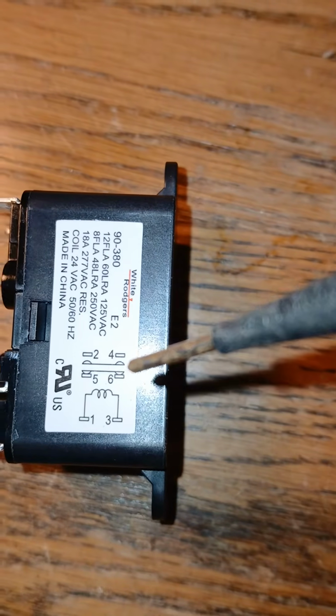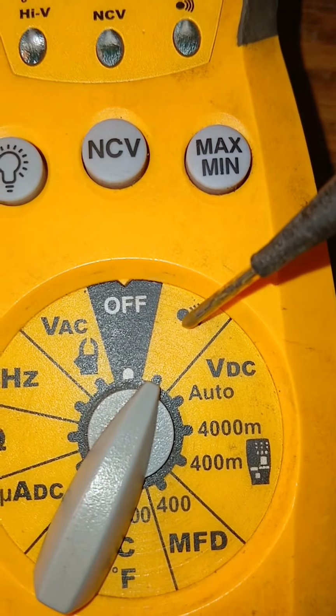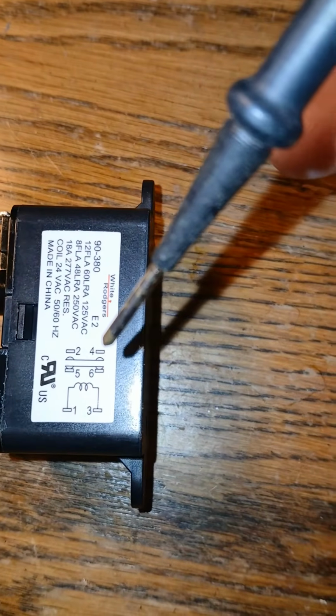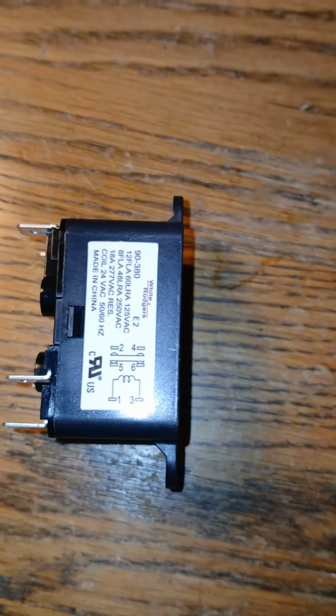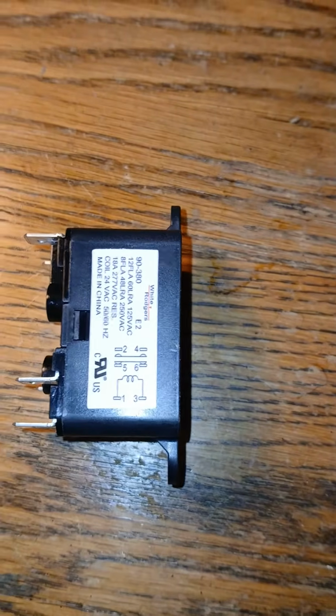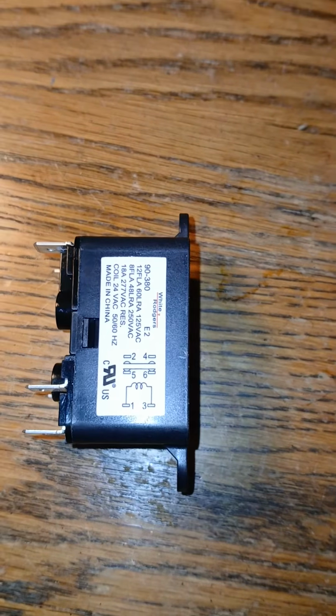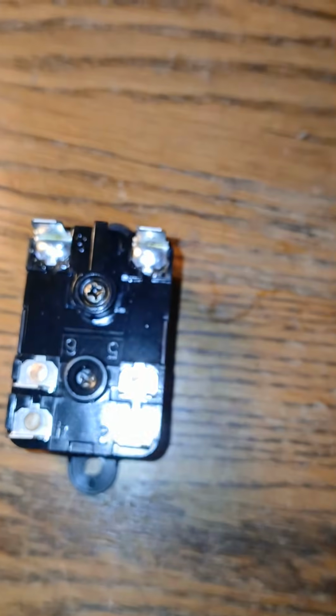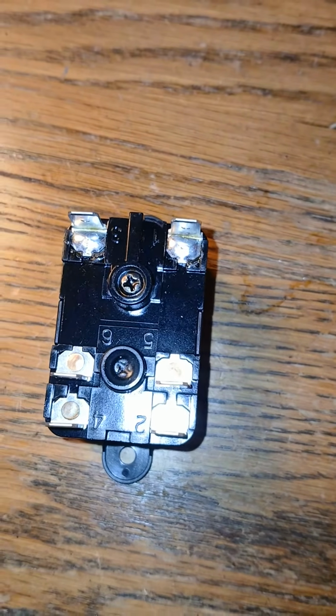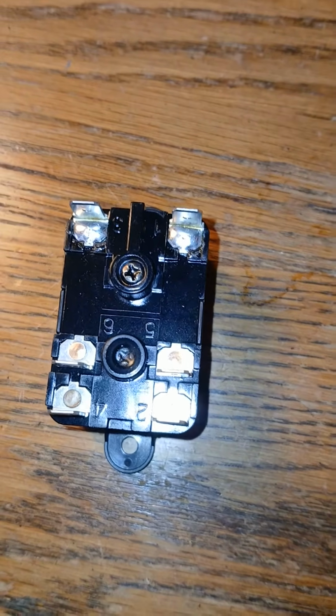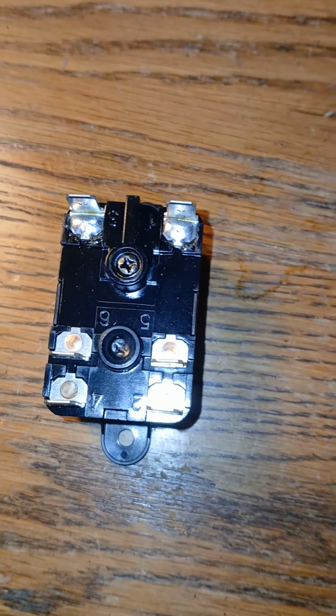So when we touched 5 and 6, we heard it beep in continuity. And again, the continuity on this particular meter is here with this little symbol. When we touched it, we heard it go beep, beep. Then 2 and 4 was open, we heard nothing. So this relay tests good. Between 70 and 80 ohms on the coil, good. On the 5 and 6, continuity, good, meaning the relay's closed. 2 and 4, relay is open. Everything is good. So this is how you test a relay.